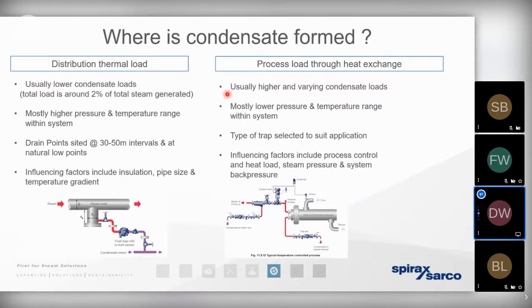Now, that can vary depending upon how wet the steam is, how far we're distributing the steam. Is it in a correctly sized pipework? Is it raining outdoors, for example? All of that can have a slight effect on the exact heat loss. 2% seems to suffice for the vast majority of sizing applications, but we always double that 2%. The 2% is what we refer to as the heat loss or the running load in a system that's been operational at a nice high temperature for a certain period of time. The infrastructure's been brought up to temperature.